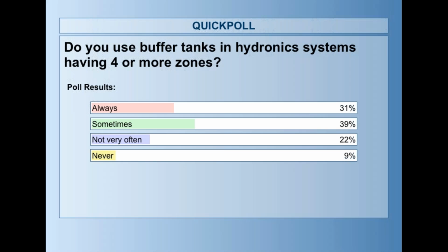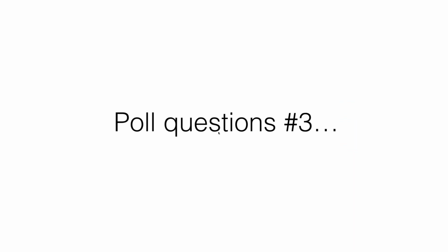And one of the nice things about an inverter compressor is that you can set the temperature you want that heat pump to produce in the chill water mode. Let's say we set it for 45 degrees Fahrenheit. It will actually ramp that compressor down to maintain that. So in cooling, in theory, we could eliminate having to chill the buffer tank down with an inverter compressor.